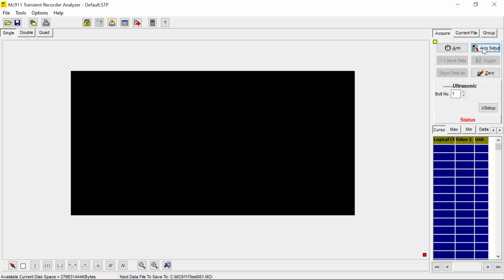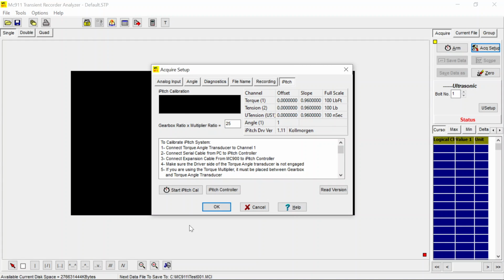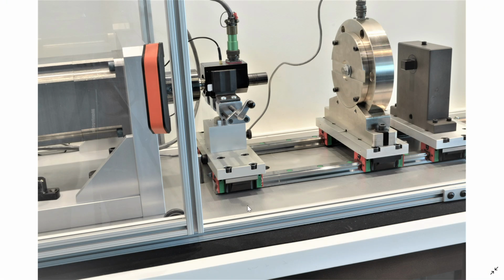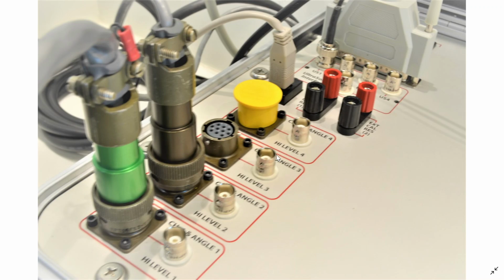Okay, and let's start with the acquire setup. Again, what we have here, before showing you what's going on, I have a torque angle transducer connected to MC950 and also load cell connected to MC950. In here, we connect the torque angle transducer to channel 1 and load cell to channel 2. Also, I've added ultrasonic connector to torque angle transducer pickup, and here we have parallel port cable hooked up to MC950, which the backend goes to the iPitch controller. Also the USB cable that's connected to the computer.